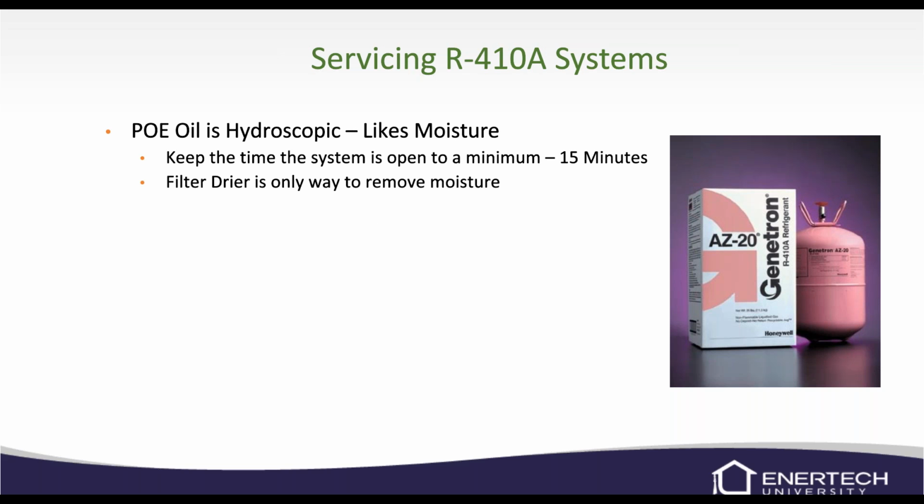Be careful when you're servicing these 410 systems. I just like to mention, we're pretty used to working on 410 anymore, but the POE oil loves moisture. So if we ever ship you oil for the refrigerant circuit, it's in a metal container because it can actually pull moisture through plastic. It's very hygroscopic, and it just loves moisture.